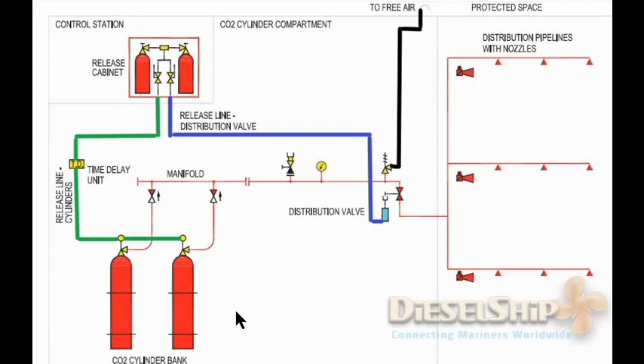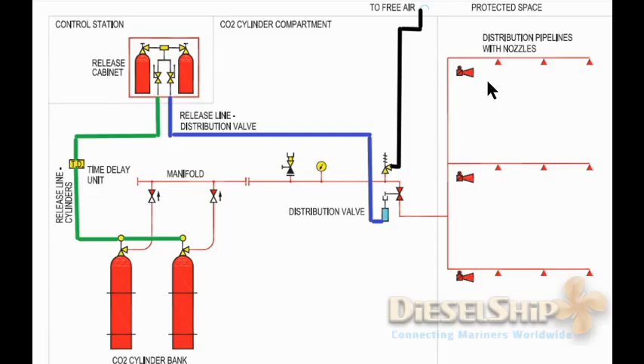Let's now concentrate only on the operation. We have the control station, also called the valve release cabinet or control cabinet. In order to flood CO2 inside the engine room, master mustering must be done first — a headcount at the muster station, order from the master — and with all confirmations per company policy, the master will give orders to the chief engineer to release the CO2. It is the chief engineer who has to release the CO2 into the engine room.